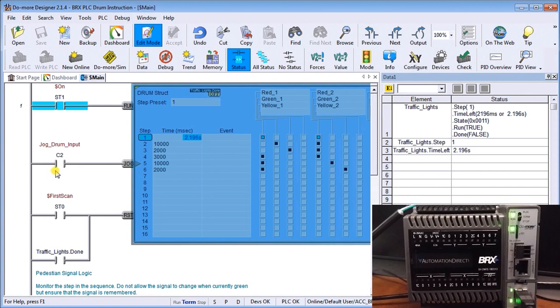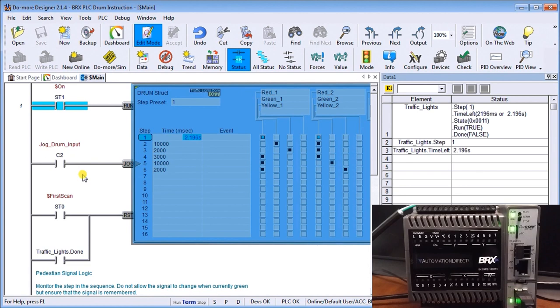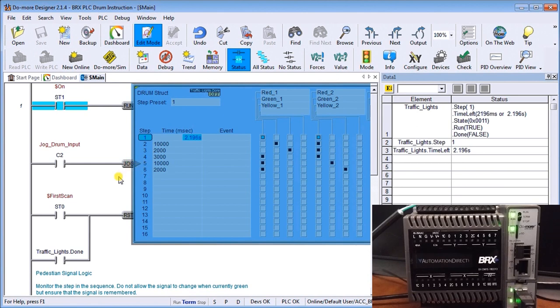What this will do is allow me as my drum is running, if I do not want to wait for the next step to occur I energize this. This will automatically jog me to the next step on a leading edge. You'll see this little arrow sign right here just means that we have a leading edge condition on that input.